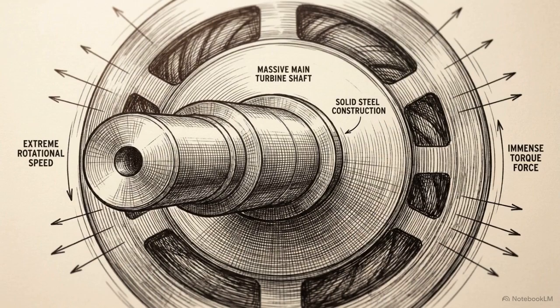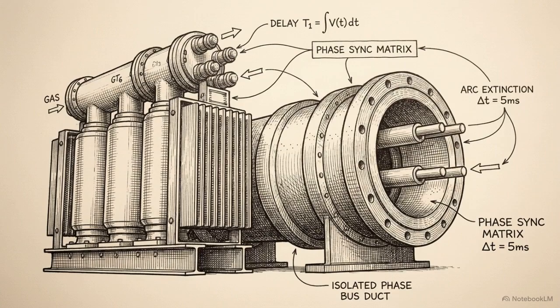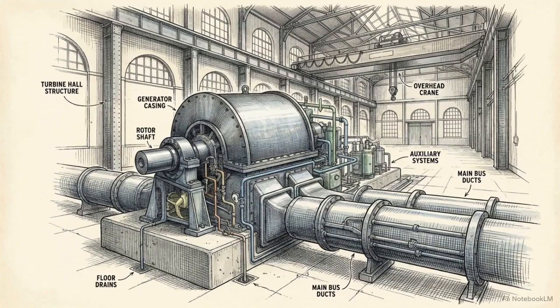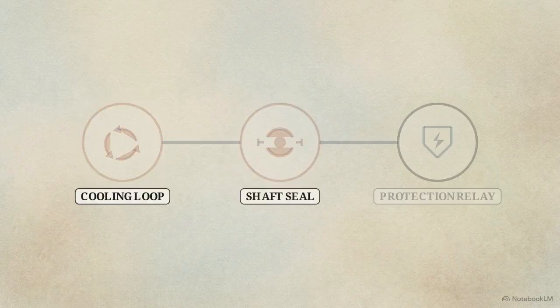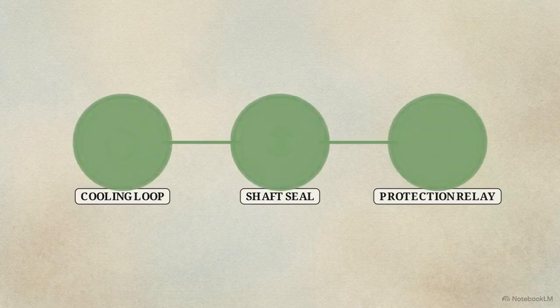Generating the power requires immense rotational force, but preventing an internal fault from cascading into total plant failure relies strictly on the precise mathematical timing of the bus ducts and SF6 switchgear. When the unit is synchronized to the grid, none of these systems function in isolation. Every loop, seal, and relay operate simultaneously, in real time.